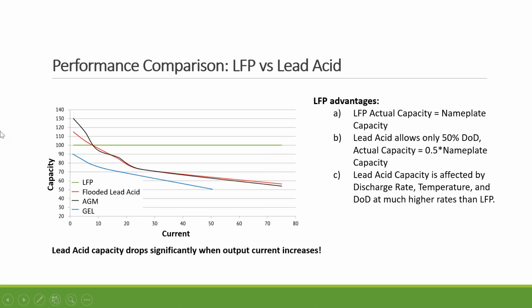So we explain economics. Here's also a graphic to show you that this happens a lot, especially if you are in the south and you need to have your air conditioning running. Here is when you use the lead acid families: when you start to draw that power, especially turning on the air conditioning, the capacity will drop very quickly. So a battery which is supposed to last for 2 hours, if you just use it normally and you turn on your AC, certain minutes later the system shuts off.